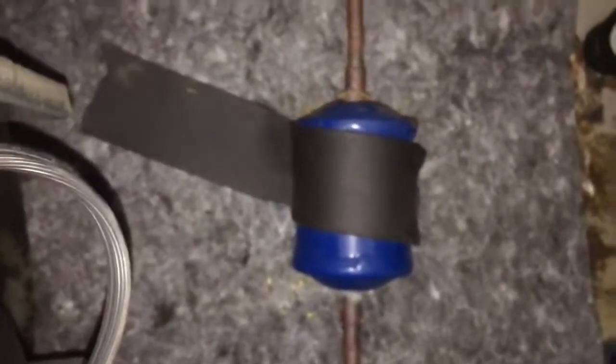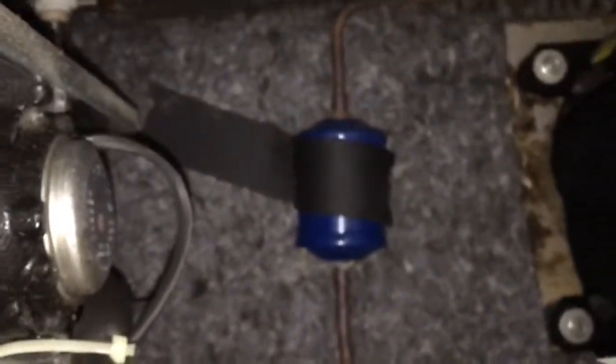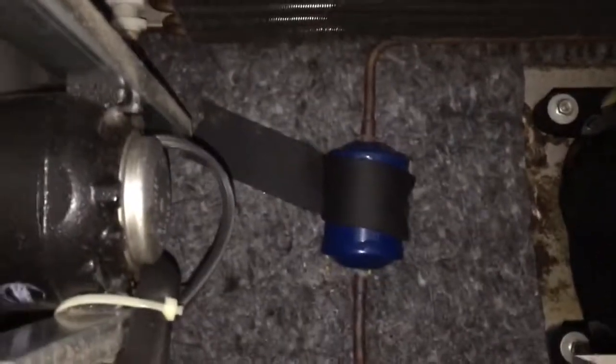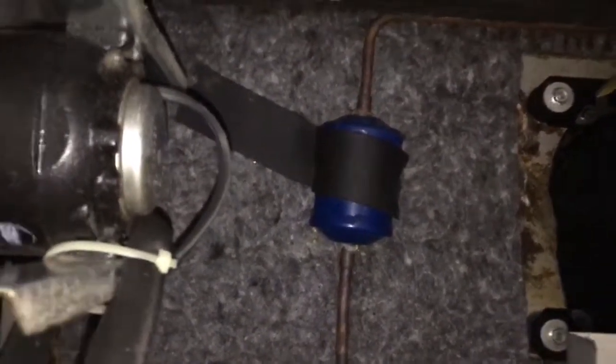This has a leak underneath the bottom of this dryer. I just put some foam tape underneath it to get it off the bottom so I can prepare the leak. Underneath the bottom of that dryer there's a 3/8ths EK-083S dryer, just sitting on the ground, rubbing steel against steel. You can see it's a little bit moist — it's rusted through the bottom of the dryer.